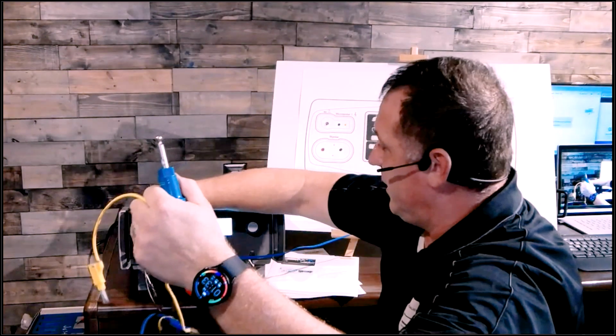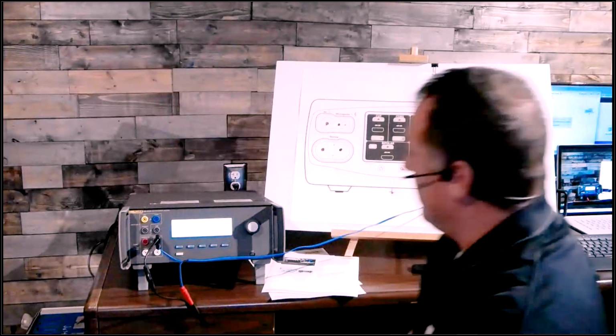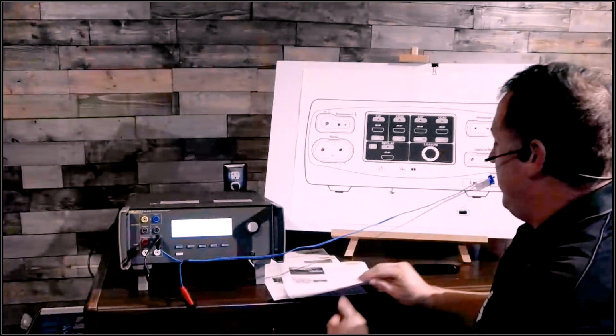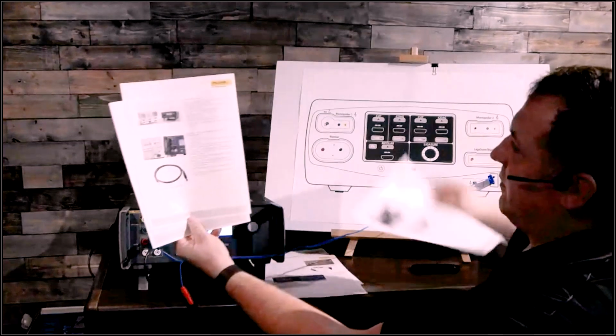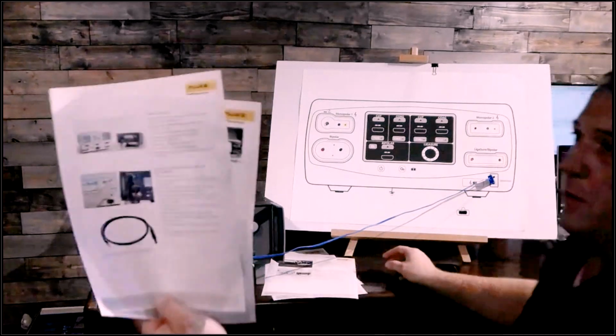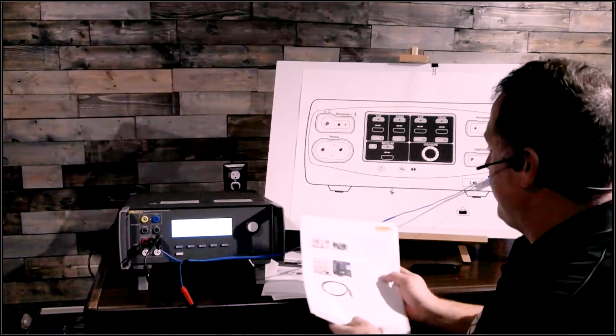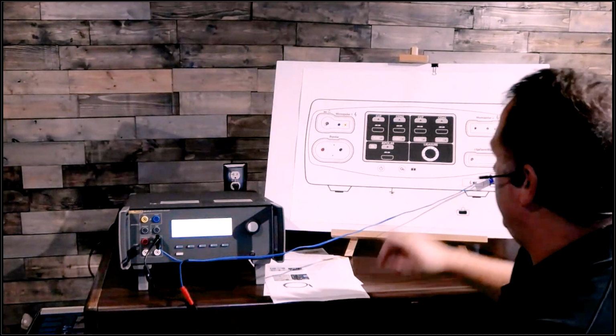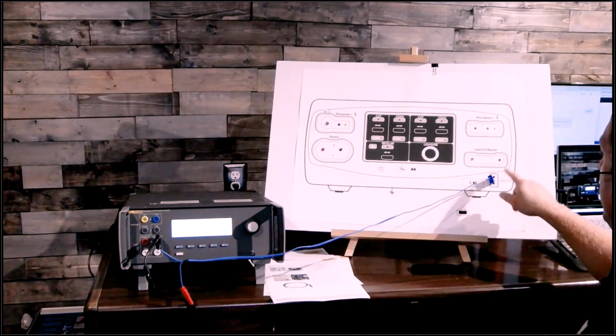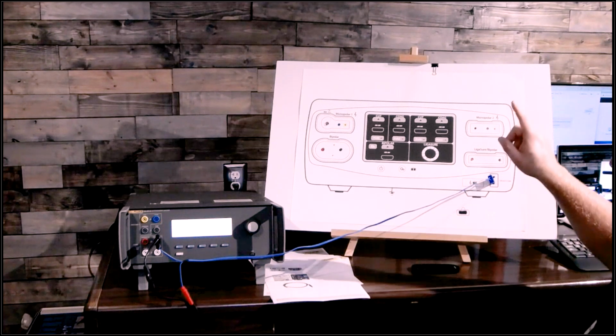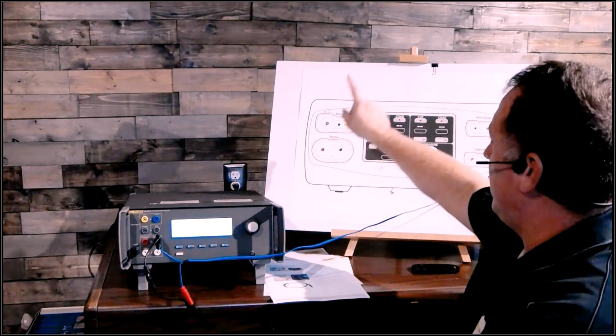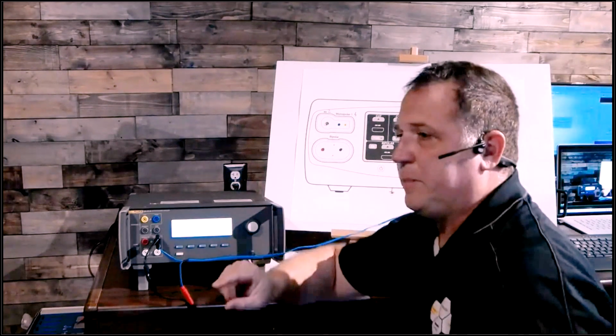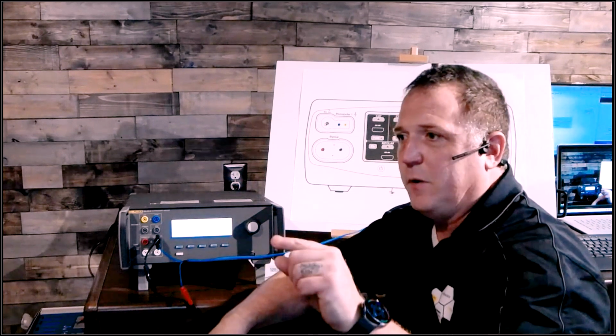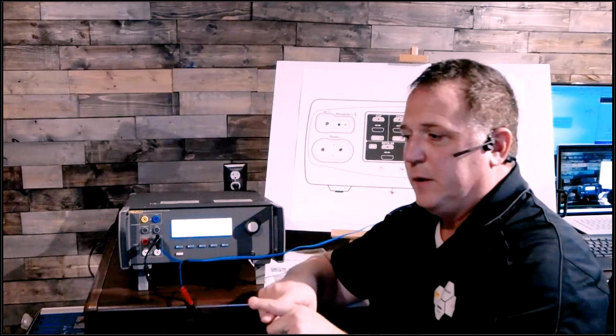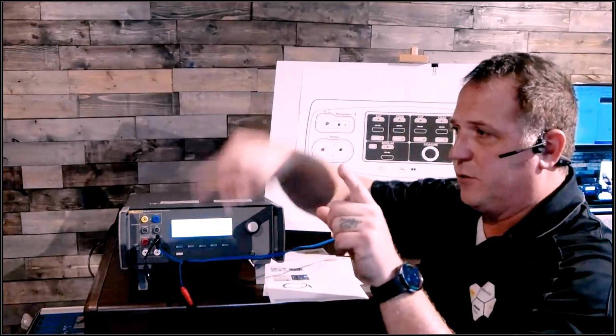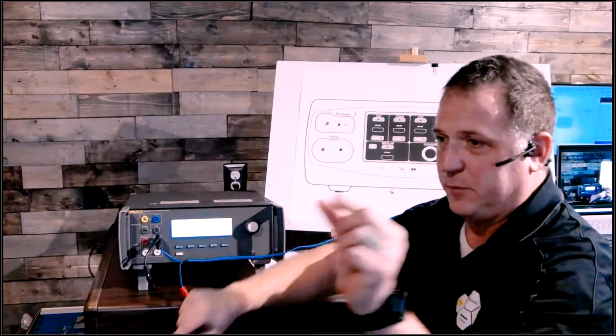All righty, here we go. So, way back in the day, oh, by the way, we're moving on to this page, bipolar connections. It's going to look like this. So, way back in the day, in the older ESUs, when you're doing bipolar, you didn't have to worry about this REM CQM. Because in bipolar, the energy that comes out of this port is alternating and going back into this port. So typically bipolar instruments look like forceps or needle nose pliers, or they'll have a loop for removing polyps. So the energy's bidirectional, AC, and it's going to bounce back and forth in between two little points.